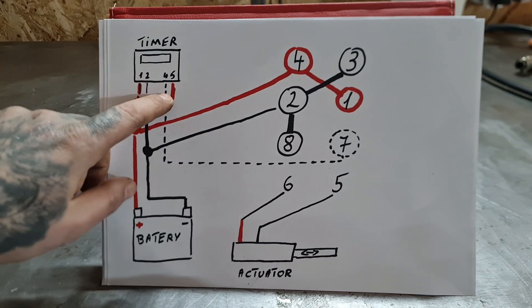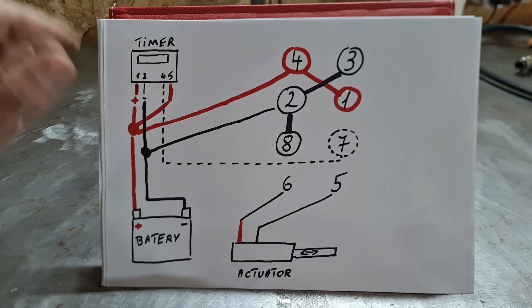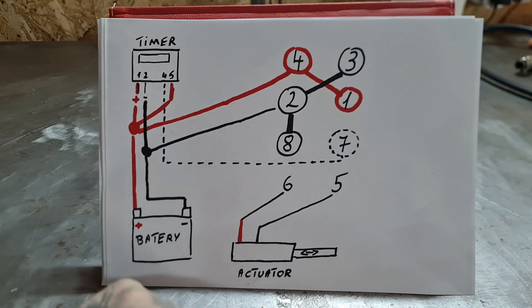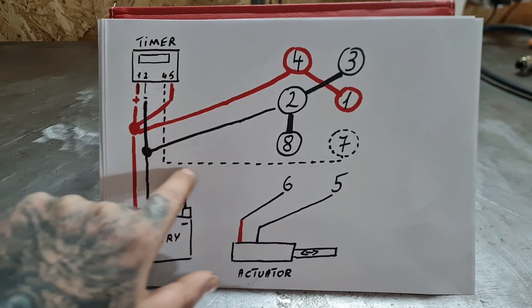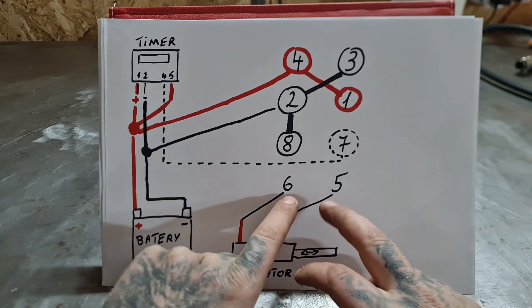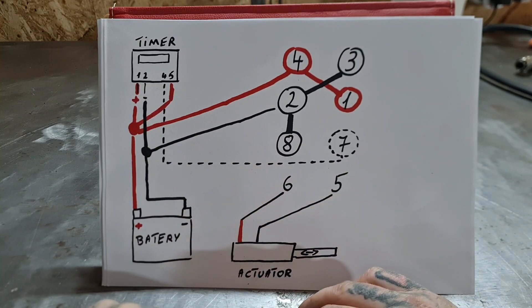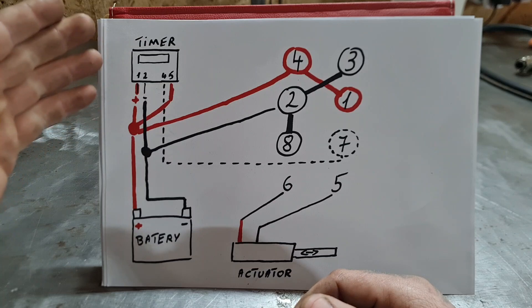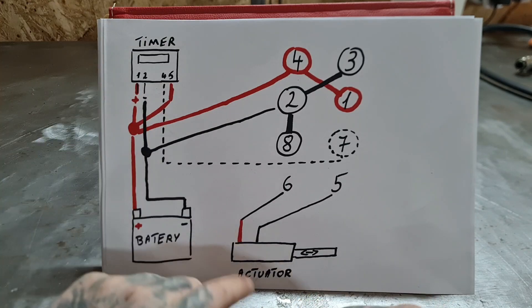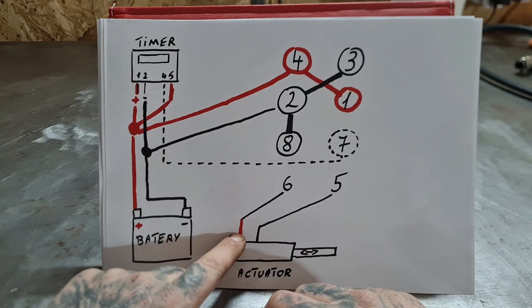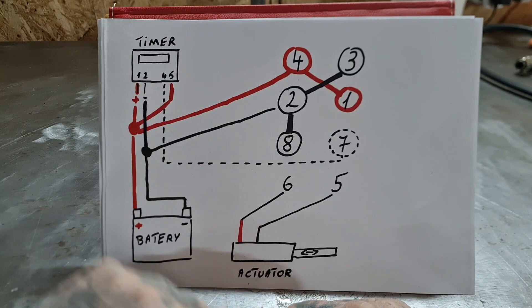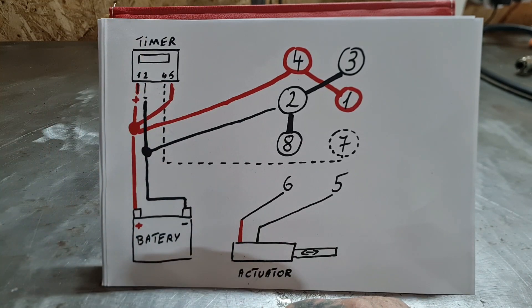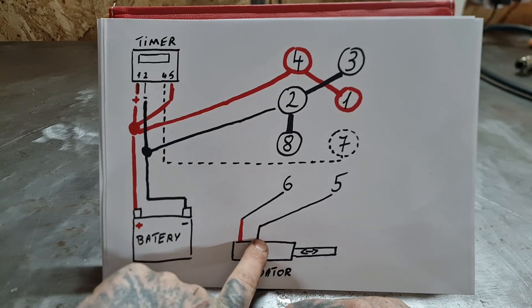For example, you set it to open at eight o'clock. This switch is going to be closed. When closed it sends a signal to seven and then the polarity between five and six switches. If before the timer is set the polarity is this is plus and this is minus, after the timer reaches eight o'clock this becomes plus and this minus, and then the actuator closes up.